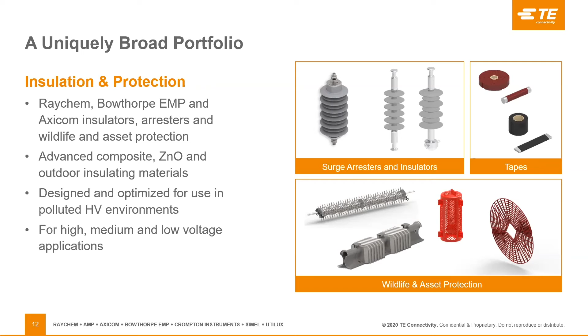I'm going to go into a case study before I get ahead of myself here. There was a problem in Central California where a crow had nested itself on a crossbar where the terminations were very close in proximity. That crow either turned its body and connected beak to tail or wingspan to wingspan and caused a failure and a fire.